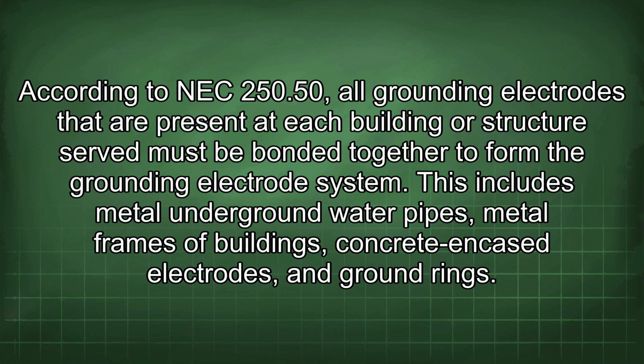According to NEC 250.50, all grounding electrodes that are present at each building or structure served must be bonded together to form the grounding electrode system. This includes metal underground water pipes, metal frames of buildings, concrete encased electrodes, and ground rings.